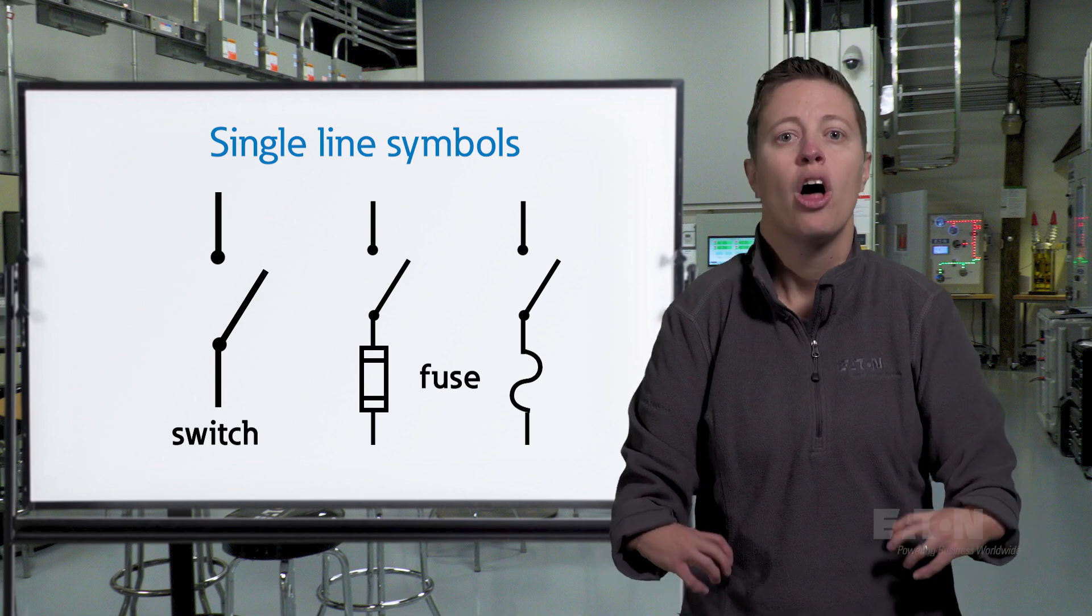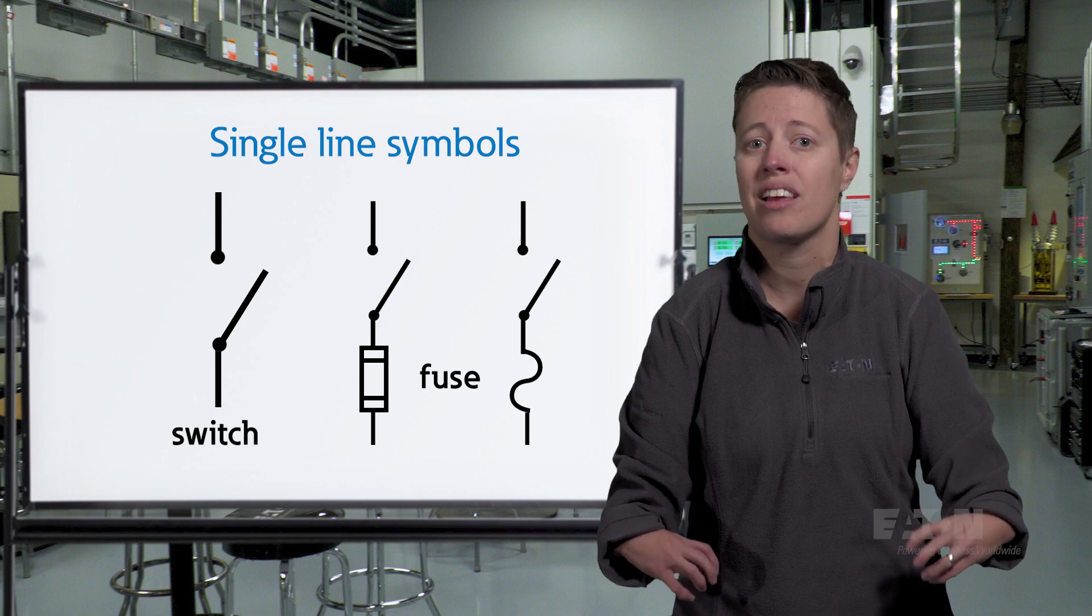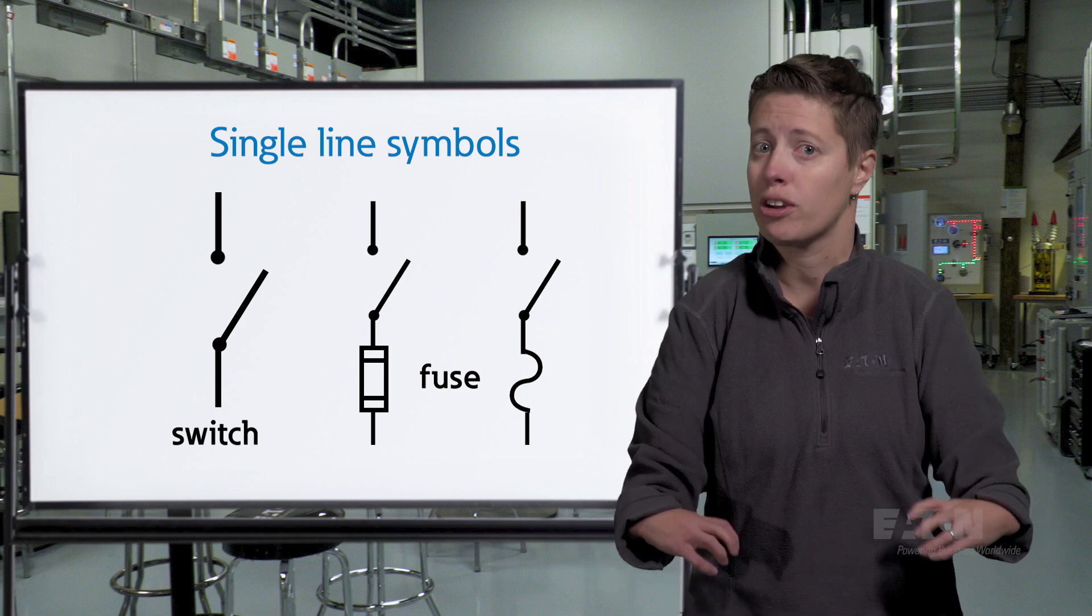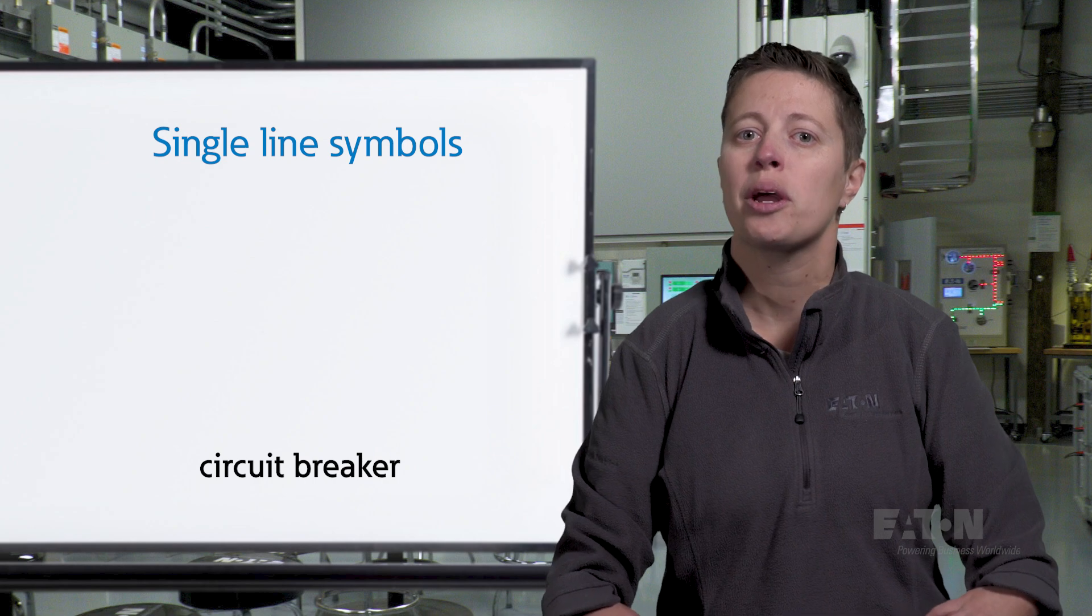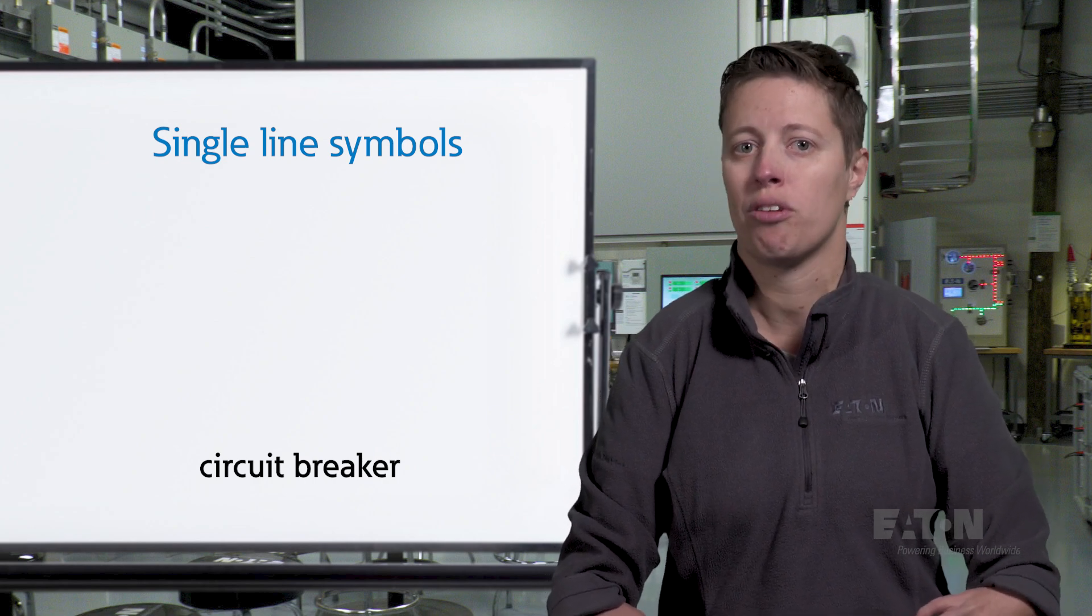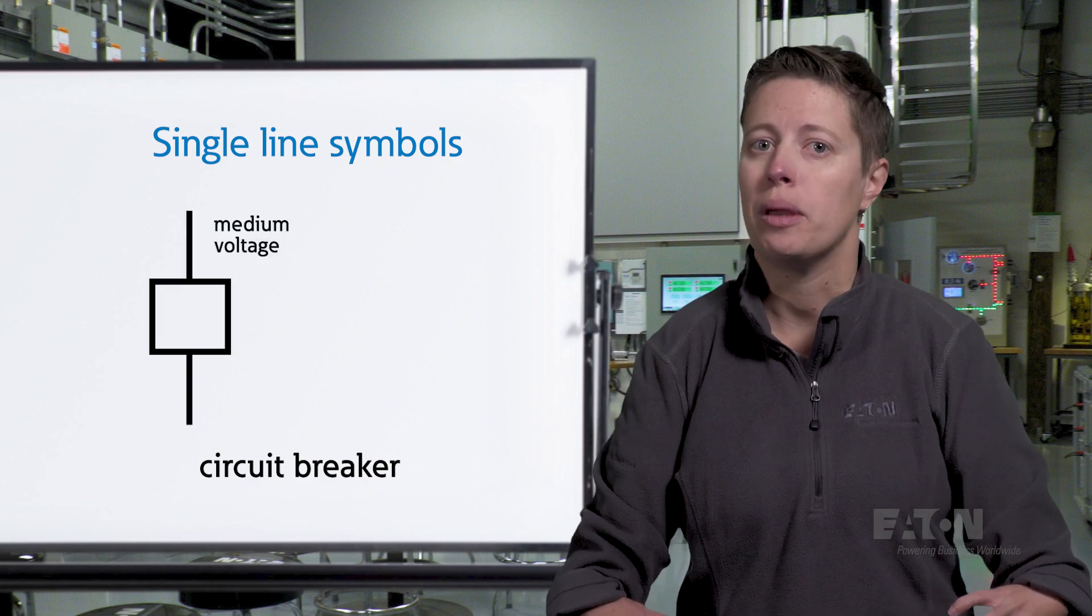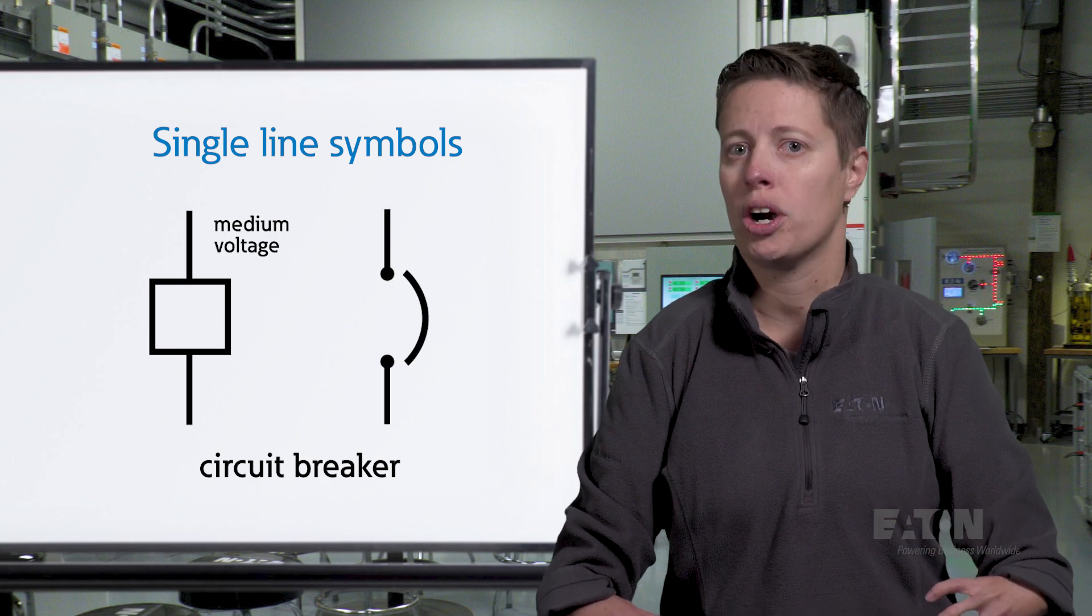Keep in mind, though we're only showing one fuse, a single line drawing represents a complete set of three fuses, one for each of the three phases. A circuit breaker symbol can look a few different ways depending on the type and voltage level. A circuit breaker may be represented by a simple square for a medium voltage breaker or by an arch bridging a gap in the conductor for a low voltage breaker.